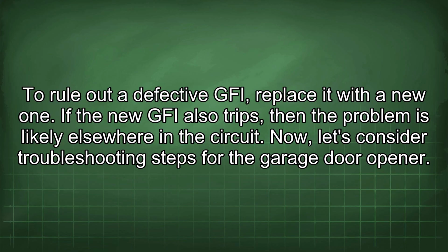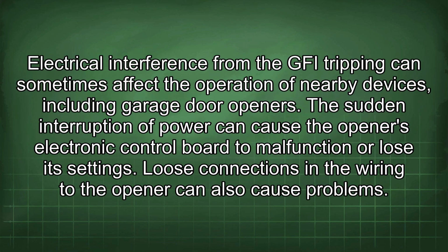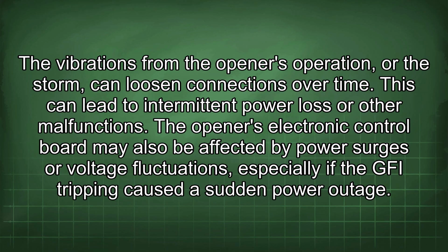Now, let's consider troubleshooting steps for the garage door opener. Electrical interference from the GFI tripping can sometimes affect the operation of nearby devices, including garage door openers. The sudden interruption of power can cause the opener's electronic control board to malfunction or lose its settings. Loose connections in the wiring to the opener can also cause problems. The vibrations from the opener's operation, or the storm, can loosen connections over time. This can lead to intermittent power loss or other malfunctions.